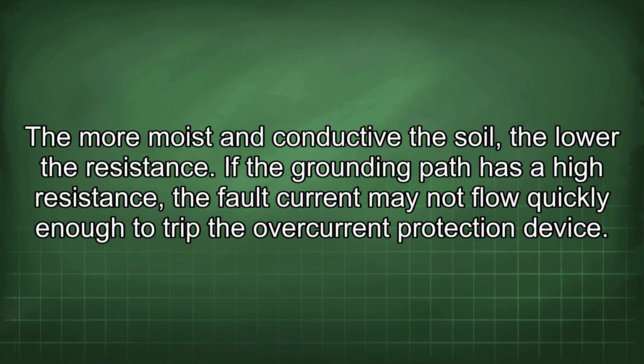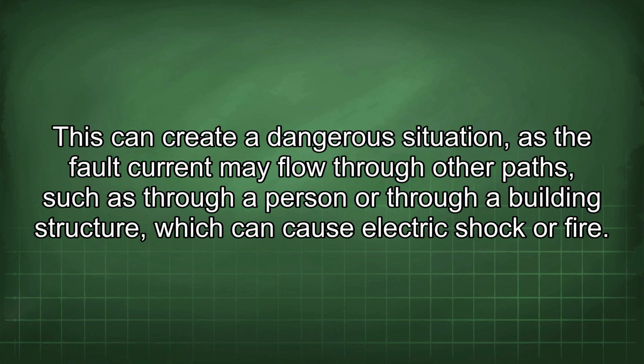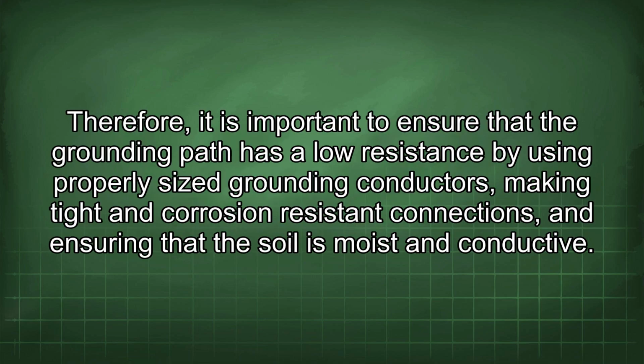If the grounding path has a high resistance, the fault current may not flow quickly enough to trip the overcurrent protection device. This can create a dangerous situation, as the fault current may flow through other paths, such as through a person or through a building structure, which can cause electric shock or fire. Therefore, it is important to ensure that the grounding path has a low resistance by using properly sized grounding conductors, making tight and corrosion-resistant connections, and ensuring that the soil is moist and conductive.